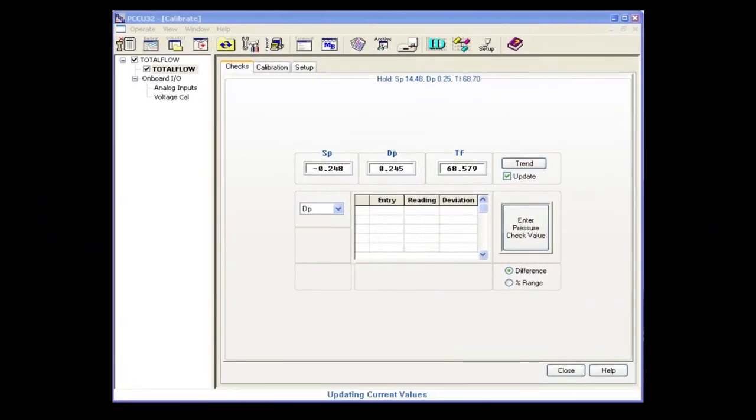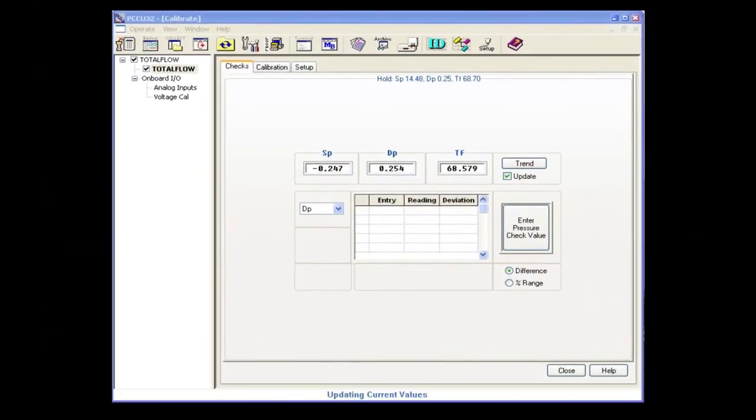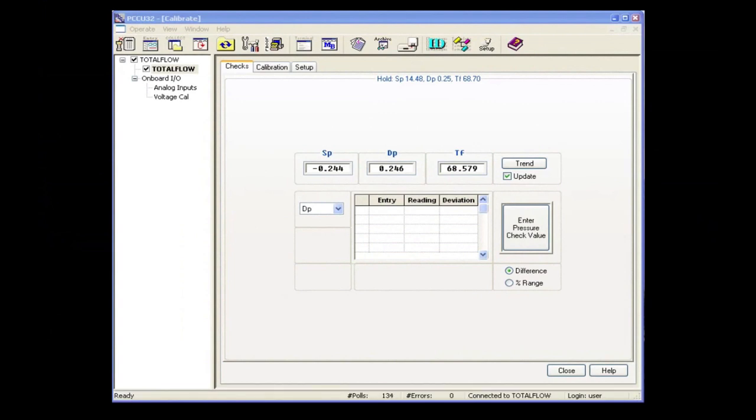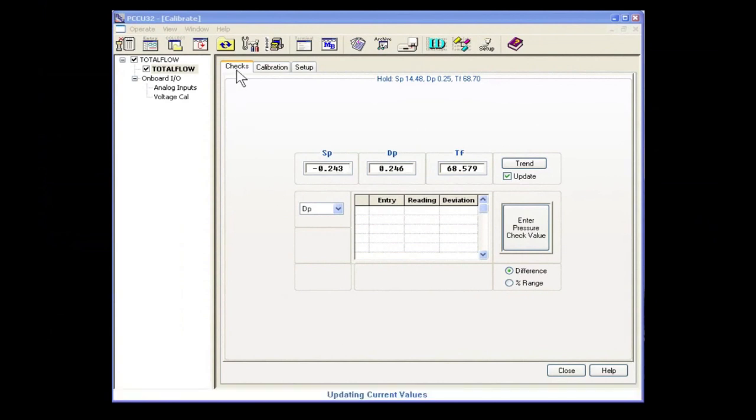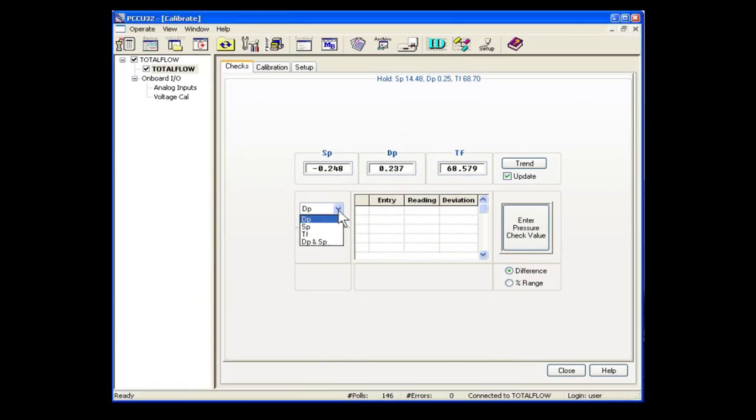In the calibration scenario we're using today, we're going to assume that the static pressure has already been calibrated and checked. So now let's move on to the DP and start with DP checks. We'll make sure we have the checks tab selected and the DP.